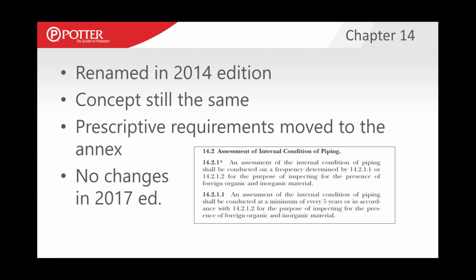And now the rule is an assessment of internal condition, and then it leaves it up to the technician, with the AHJ's input and the owner, to figure out the best way to assess the internal condition. If you go to the annex for section 14.2, all those options for complying with this section are now listed in the annex. So there are a lot of different ways to comply with this assessment of internal condition. None of these really changed in the 2017 or even the 2020 edition. So it's been the same since 2014. No longer an internal inspection, but an assessment of internal condition, and there are many ways to comply.